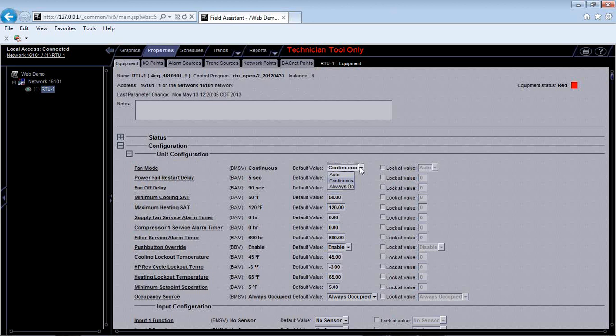It's going to run 365 days, 24/7, always on. That's what that means, okay? Continuous means that I'm always going to run the fan when I'm in occupied mode. Okay, so when my schedule says I'm occupied, I'm going to be running the fan. No matter if it needs heat or cool, or if I'm satisfied, my fan's still going to be running. And then the third option, auto, means that I will only run the fan when I have a call for heating or cooling or economizing. So whenever my space temperature is out of whack and I need some air, I'm going to turn my fan on. Okay, you can select which option you want. You can confirm it with the end user, or if you're the end user, you can select it, but we give you the option of how you want to control that.